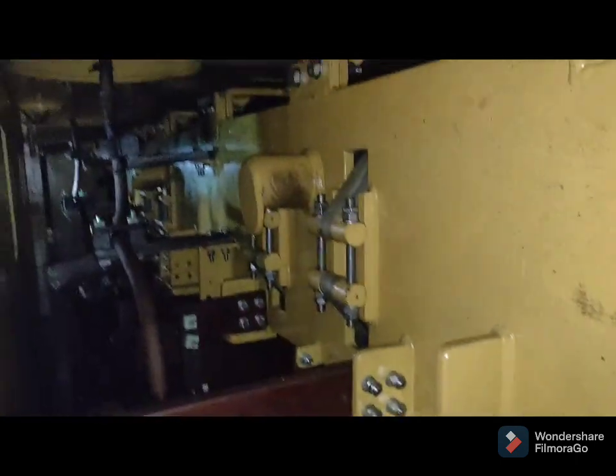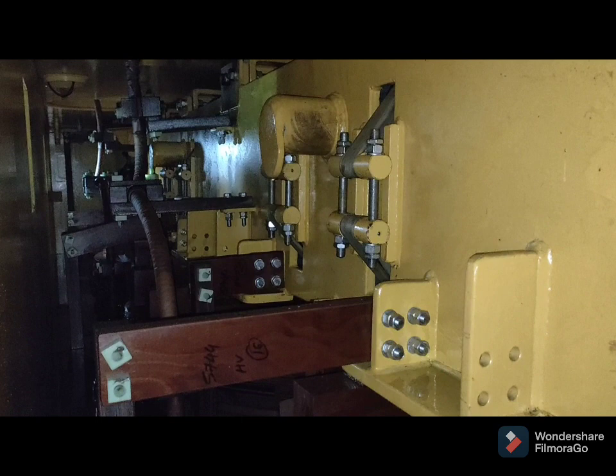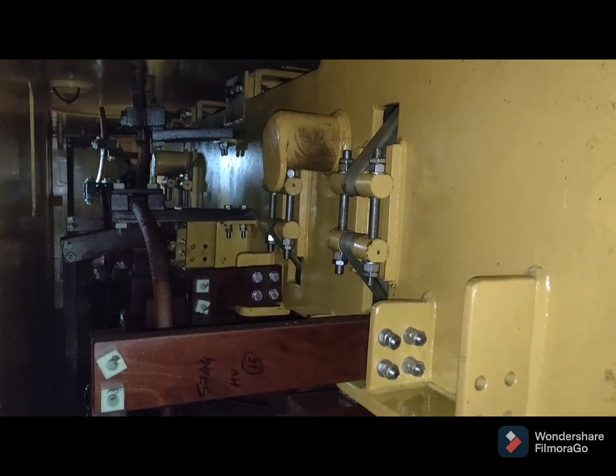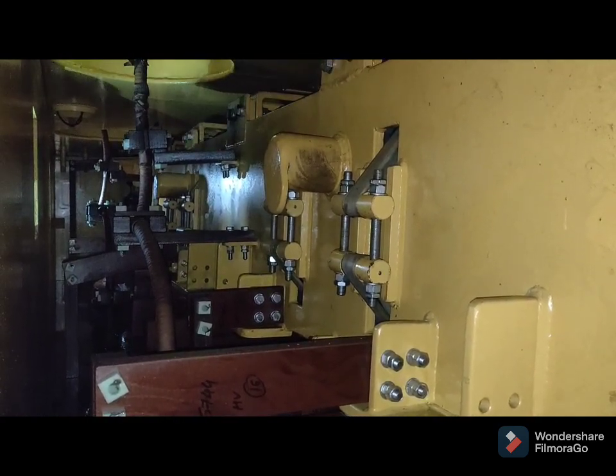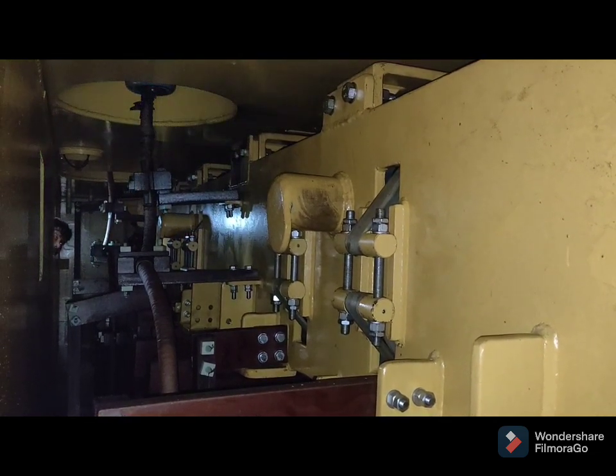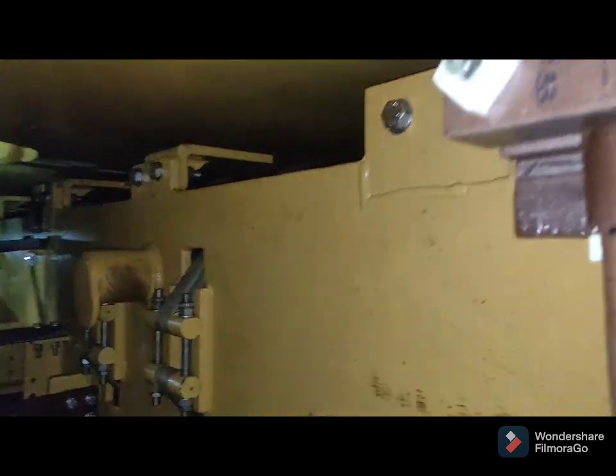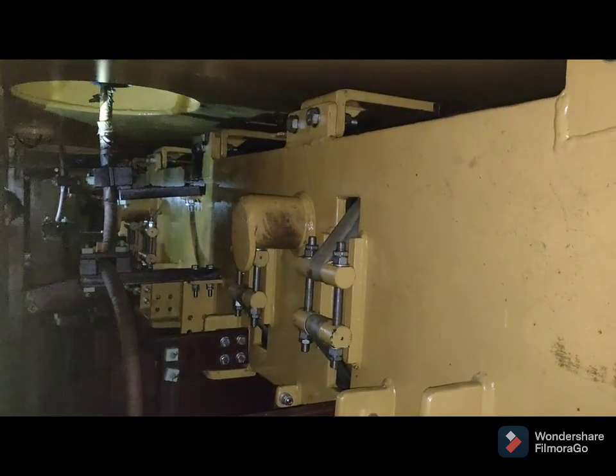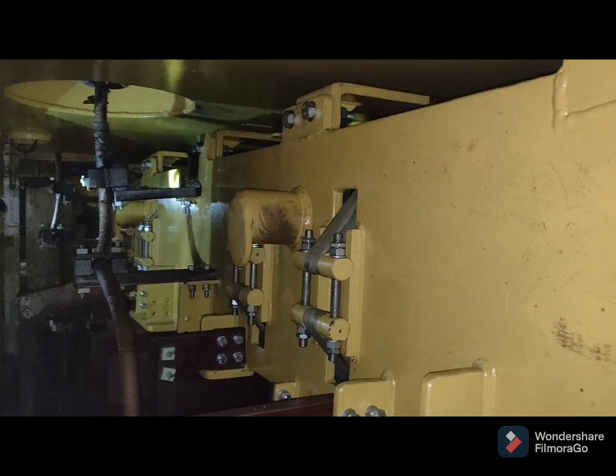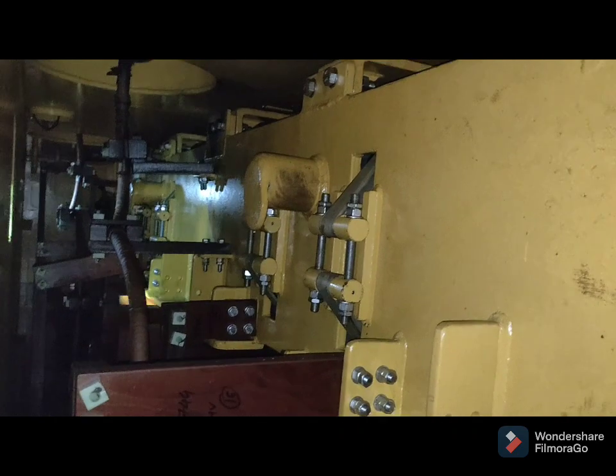These are the inside tour of the transformer. You can see the first the blue lead, this is the yellow, and the last lead is the red lead. All the wooden supports from the body are provided for insulation purposes. You are seeing the damaged lead, and this is the good lead and the good epoxy of the bushings.